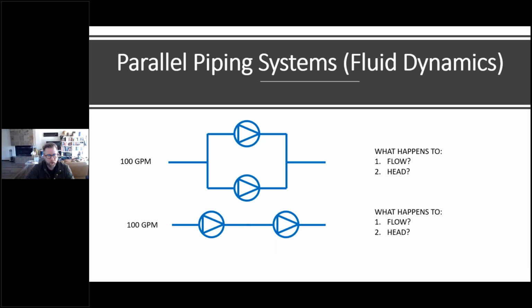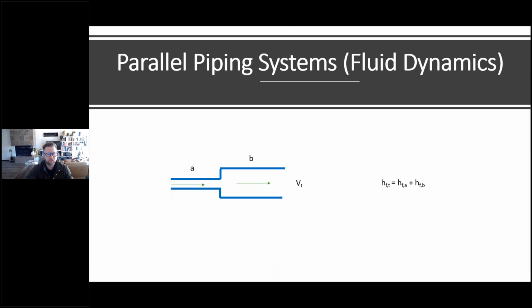So if we have two pumps in parallel, each pump is the same pump, and only one pump is on, and we turn the second pump on. With two pumps in parallel, the second pump turning on, same pumps, the flow will double and the head across the system will stay the same. If we switch that configuration to two pumps in series and we turn the second pump on, your flow will remain the same and your head will double, basically, will increase. So that is the difference in those configurations. And we want to remember this when we talk about parallel piping systems.